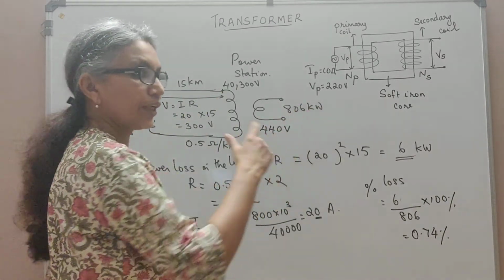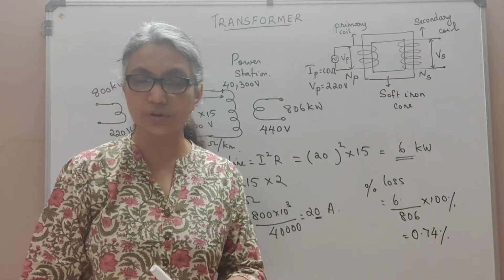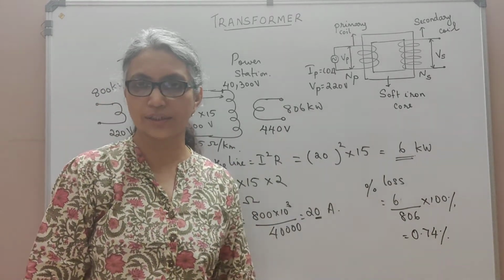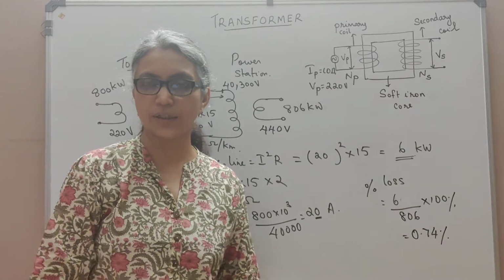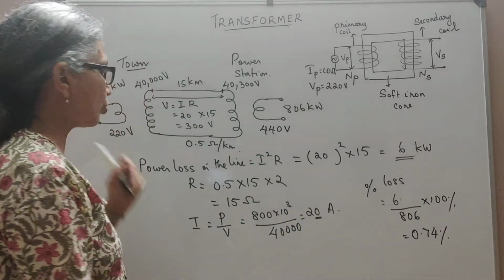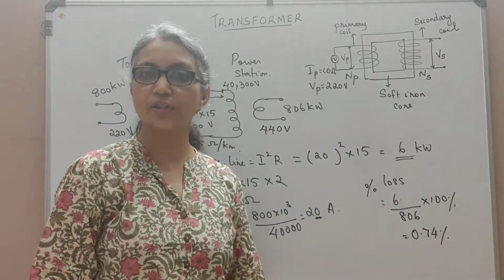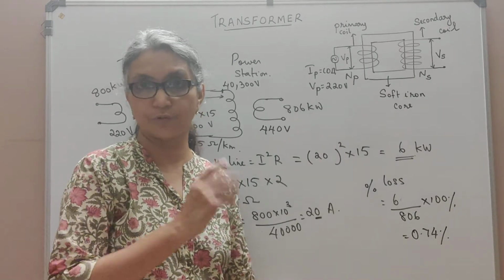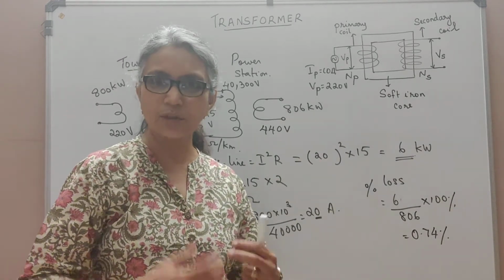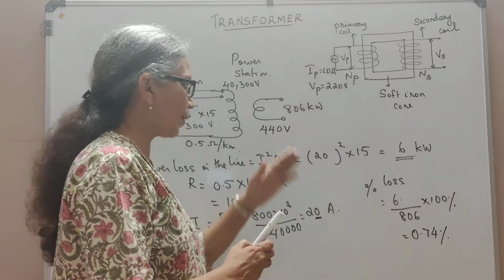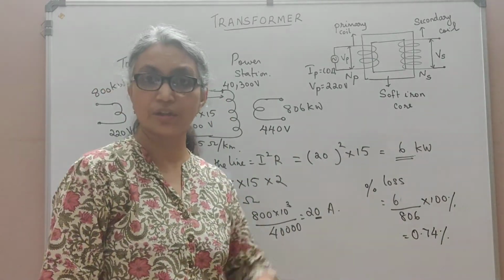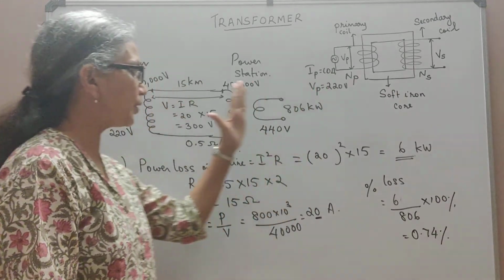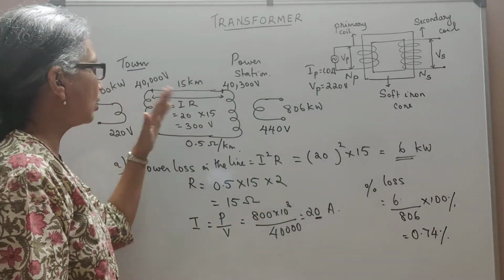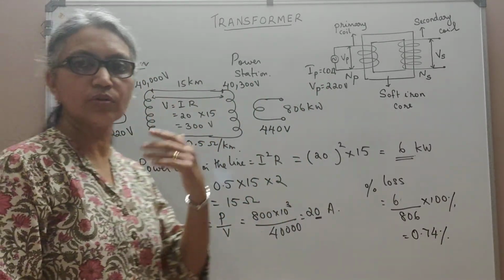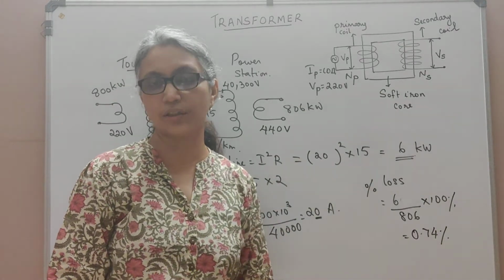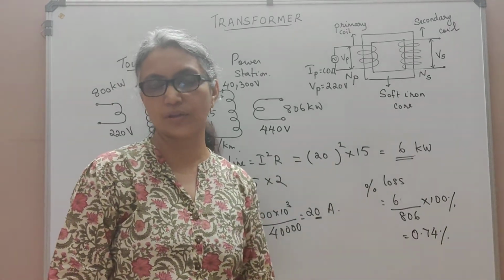So out of the 806 kilowatt that is produced, only 6 kilowatt is being lost as heat during transmission. The remaining 800 is given to the town, which reduces the percentage loss to 0.74% from 43%. This is basically why we need to step up voltages at the power station to high voltages, transmit at high voltage and low current, and then when it reaches the town, you have to step it down to 220 volt before supplying it to the consumers.